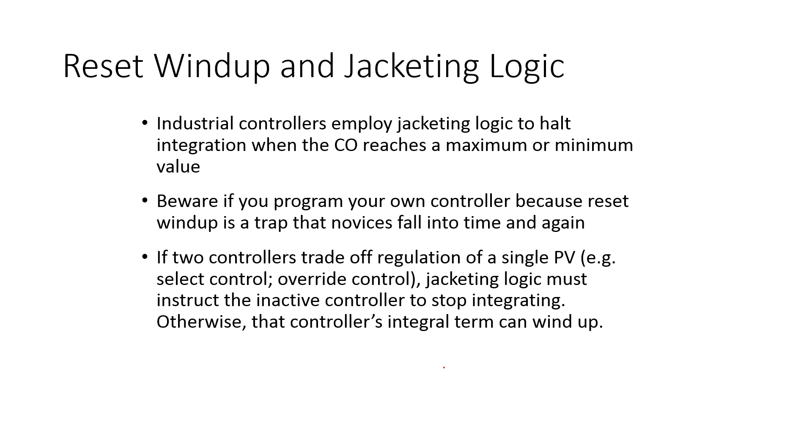One of the things that we can do with anti-reset wind up is limit the value of that integral term. Most times in most algorithms, they just stop accumulating the integral term if the manipulated variable is saturated. So a manipulated variable might be saturated, let's say for a valve, between 0 to 100%. And if for whatever reason, the value of my controller output is 0 or 100%, then it just stops accumulating that integral until it comes back to a more acceptable level.